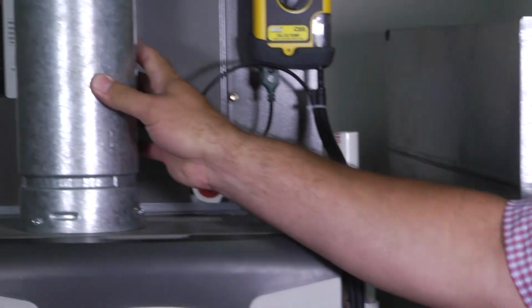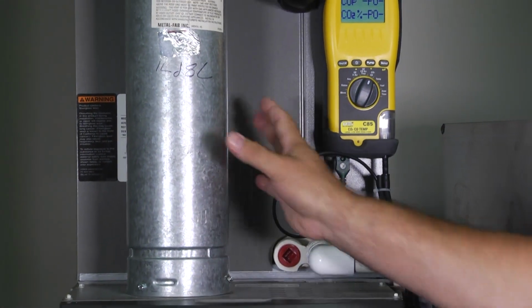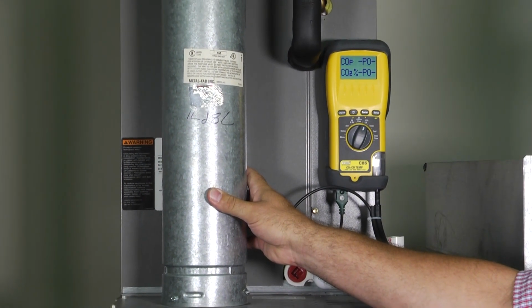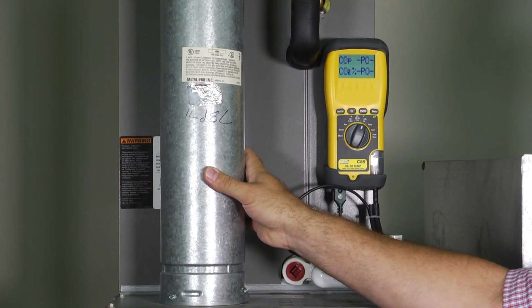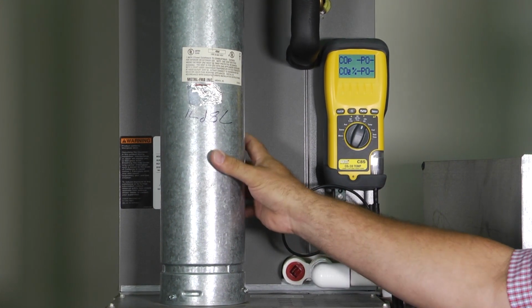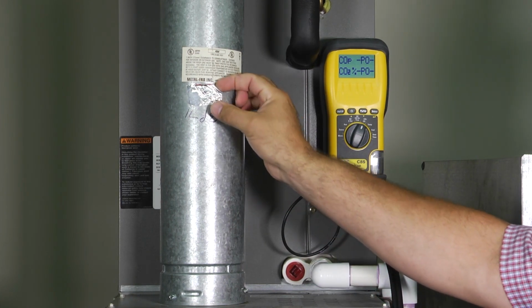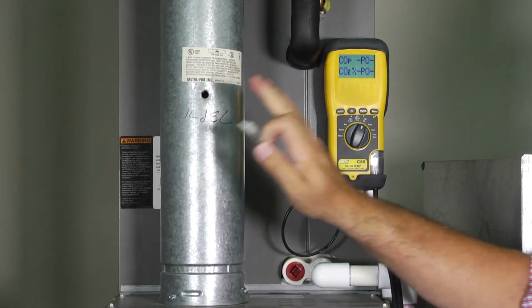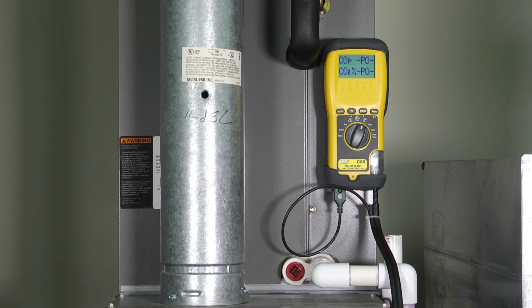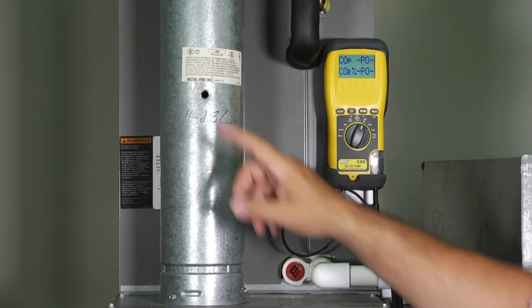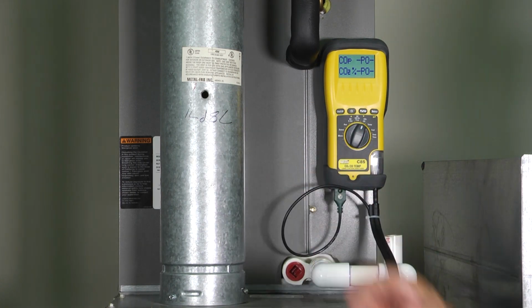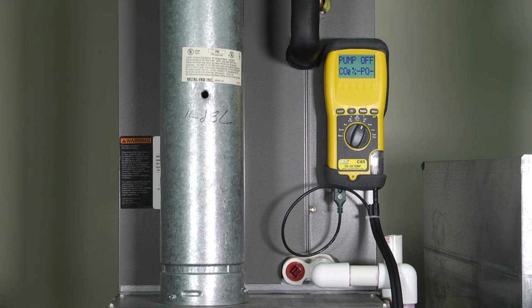Now this particular furnace is what we call an 80% efficient, so it's running off B-vent, or B-vent venting on it. Now the thing to remember about B-vent is that here in our lab, we've actually gone and drilled a hole inside the venting. You are not going to do this in the field because that is now damaging the double wall that goes inside of it. And you say to me, Mark, that's great, but how am I going to drill my hole into it?